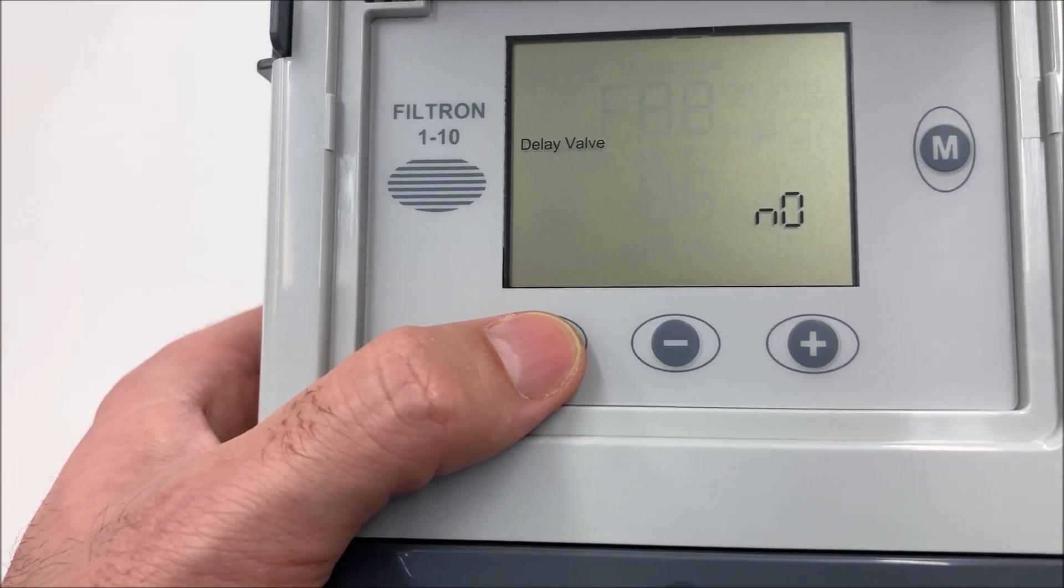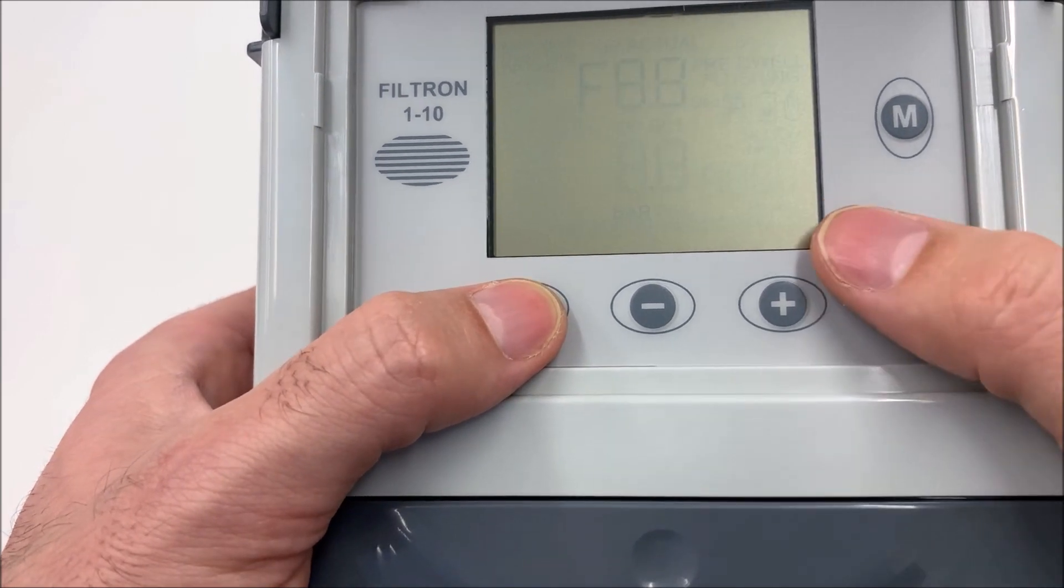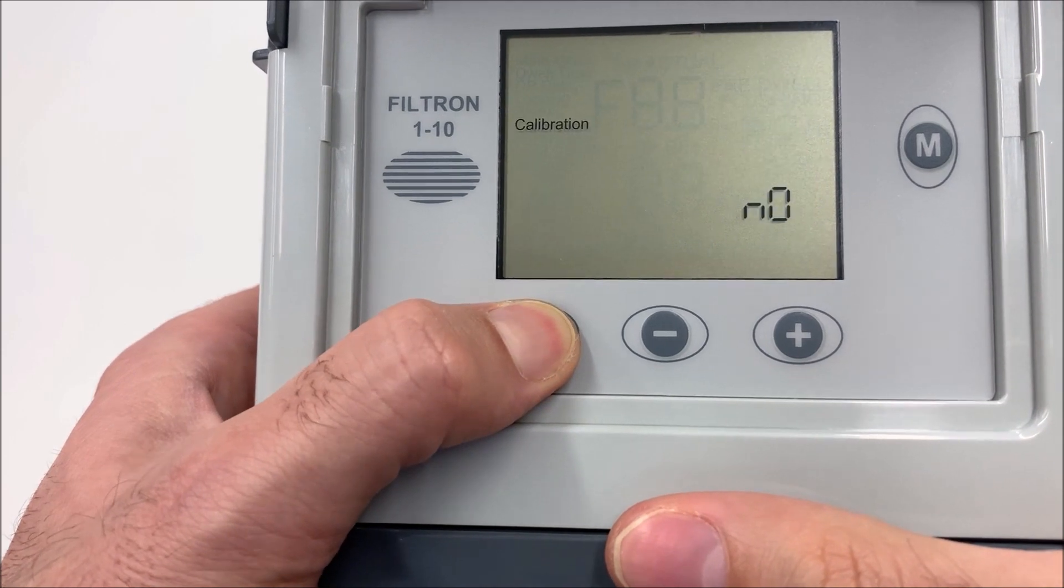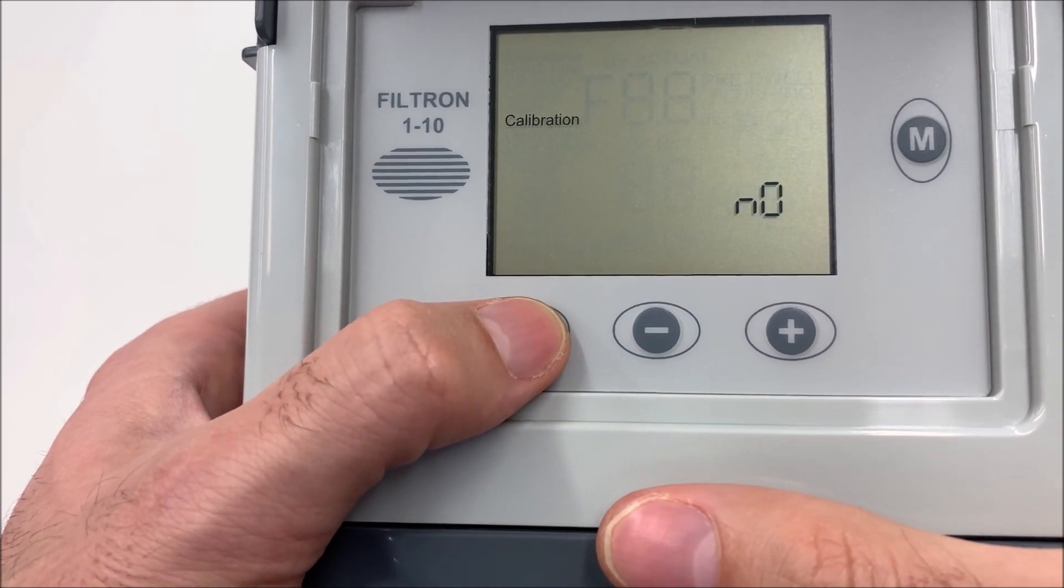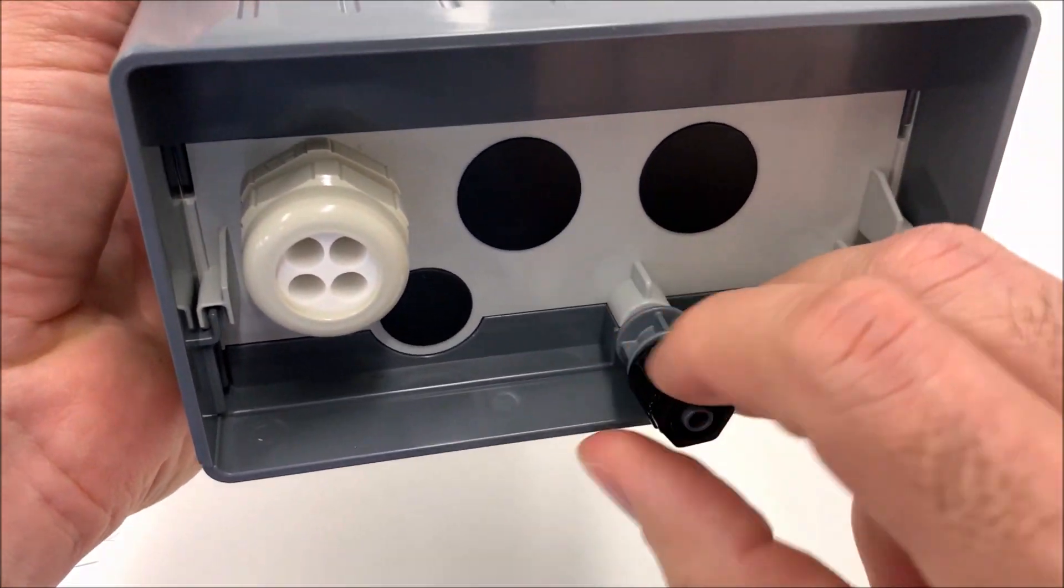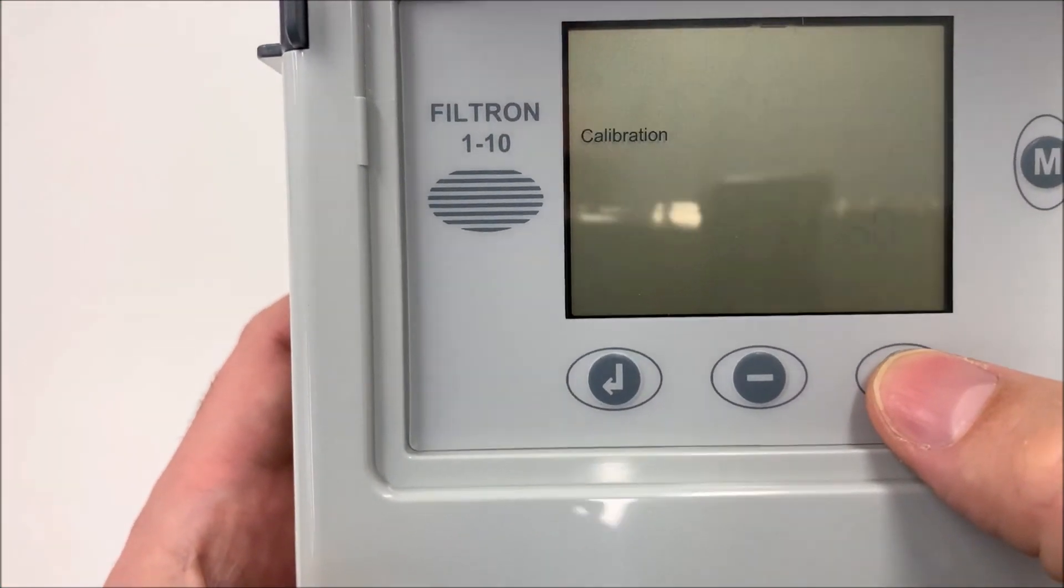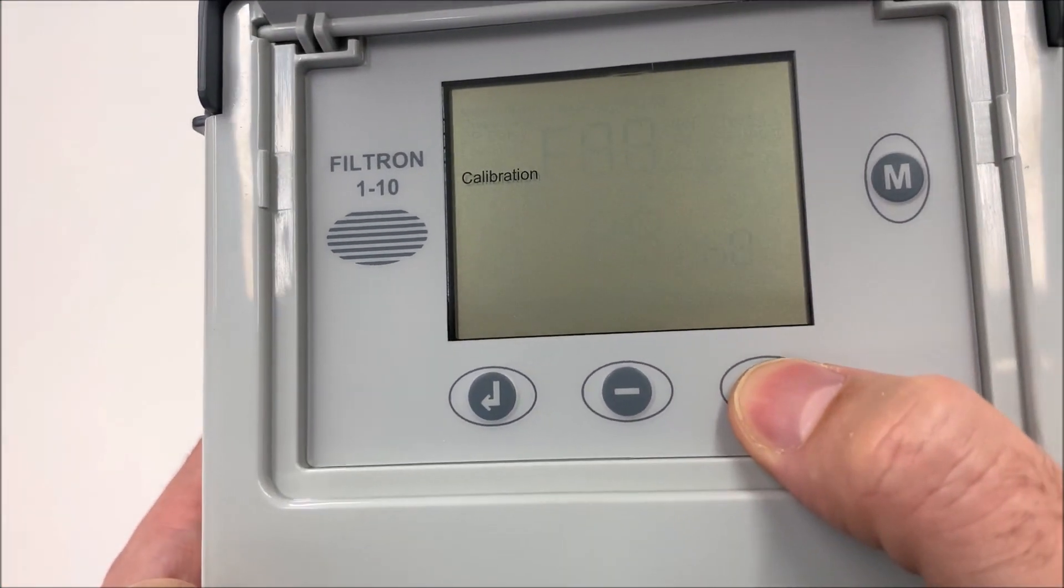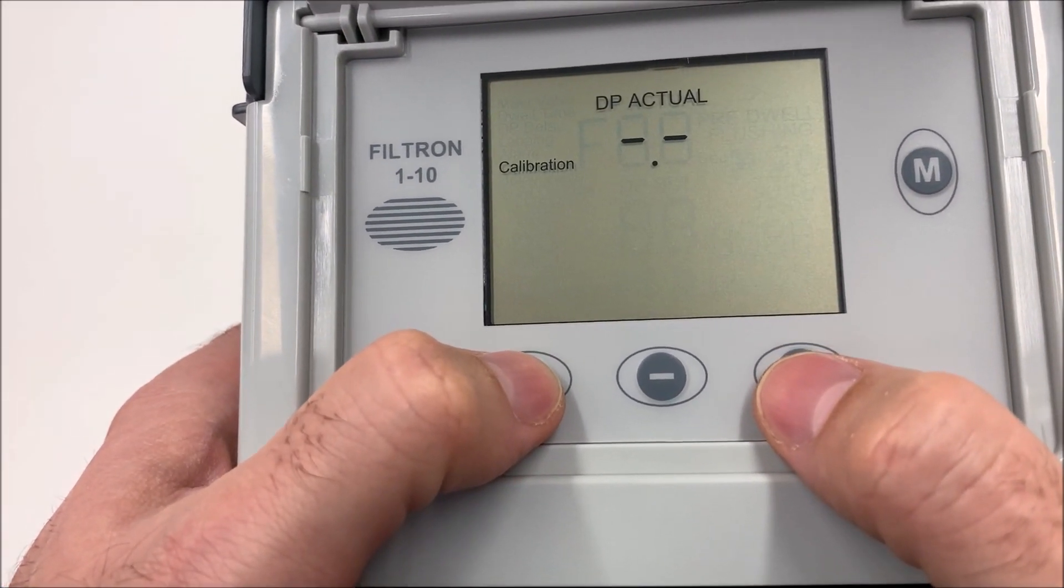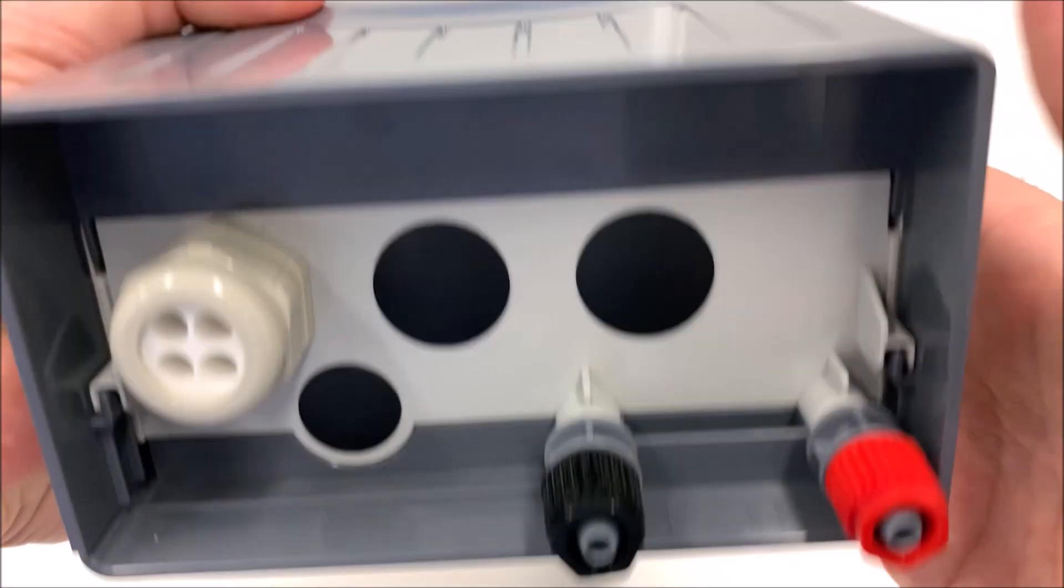Delay valve. Forget this parameter. View outputs also. Forget it. We can change the pressure to PSI or bar. Calibration. We can calibrate the PD switch. To calibrate, we need to disconnect the two microtubes to open air and then we put calibration here. And we will calibrate. Done. The calibration now is done because the two microtubes will be to the atmosphere.